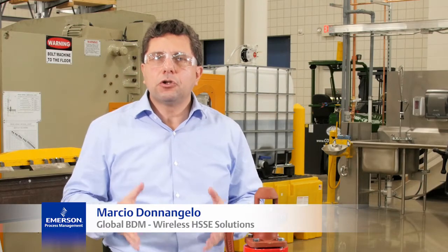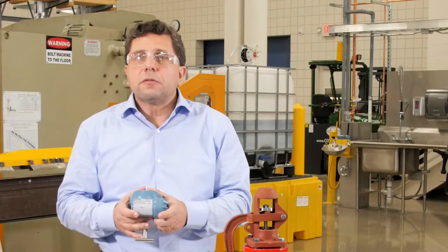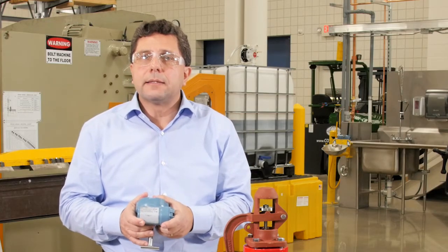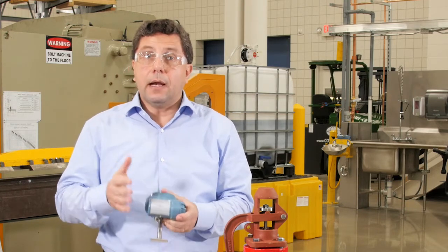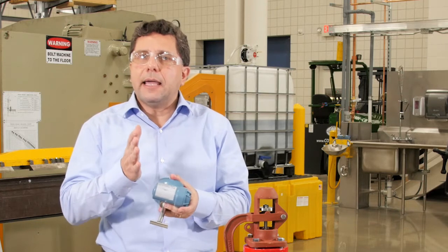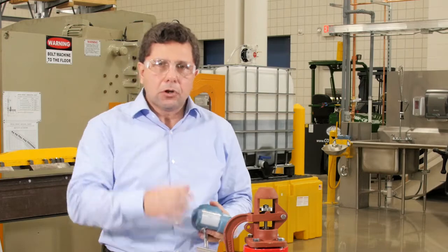Hi, I'm Marcio Donnangelo with Emerson, and I want to show you how you can monitor a pressure relief device in a non-intrusive way without disrupting your process. The Rosemount 708 wireless acoustic transmitter can identify when a release has started, when it stopped, and also whether the relief valve is leaking or simmering. Let me show you how it works.